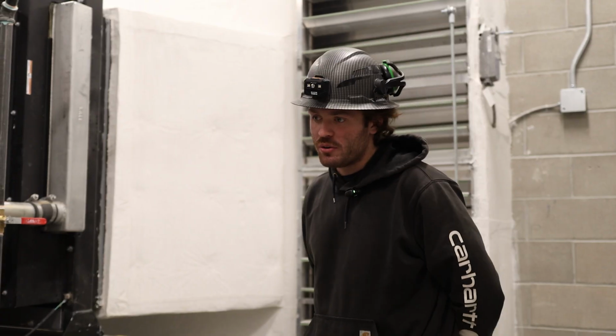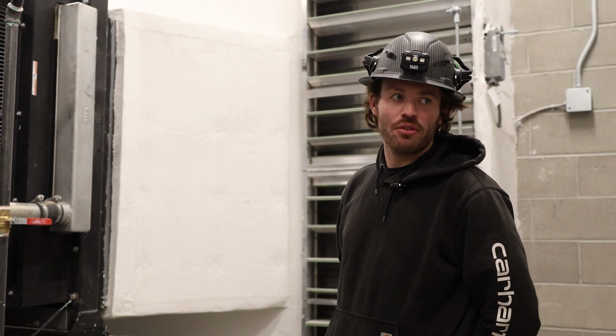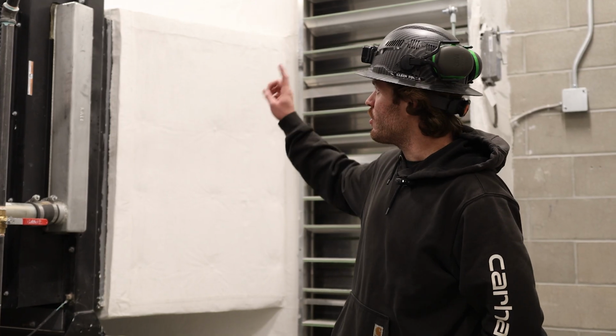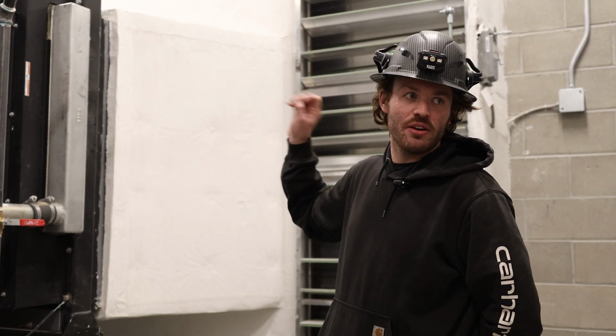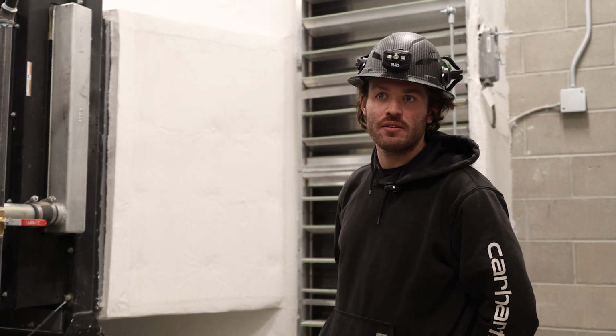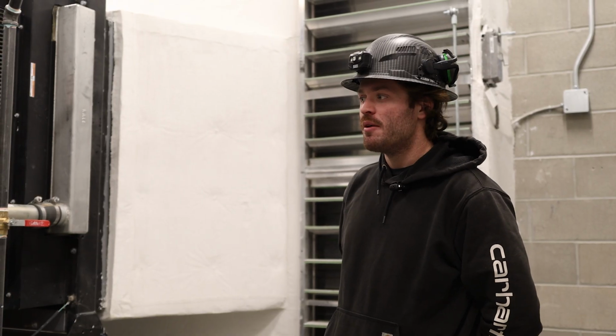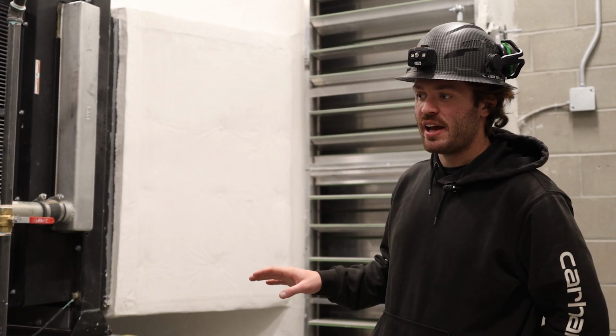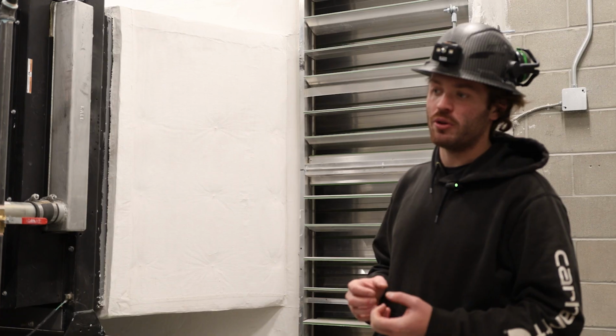For fuel level on the unit, if it is above 90%, it will throw a high level warning. This is done so for a light on the outside of the building to give an indication to the fueling driver to stop fueling the unit, for expansion in the tank. When the fuel increases in temperature, the level will increase. That's why we want to keep it not really any higher than 90%, because of the risk of overfueling it if it got hot.